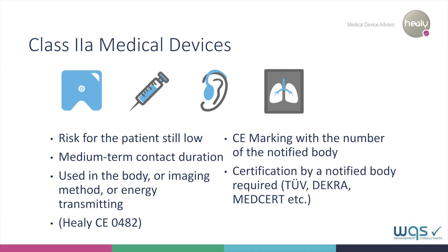Class 2A devices are different. The user risk here is still low, but the duration of application is medium term, and the application takes place within the body, either by imaging methods or by transferring energy to the body. Other examples are the application of toothpaste in the mouth or an injection with a drug. This is the class where Healy is to be found. The duration of its application can be determined as medium term, and the application of microcurrent for therapy is transferring energy to the user's body. All products in this class bear the CE mark of a notified body, such as MedCert, which means that the manufacturer is certified.